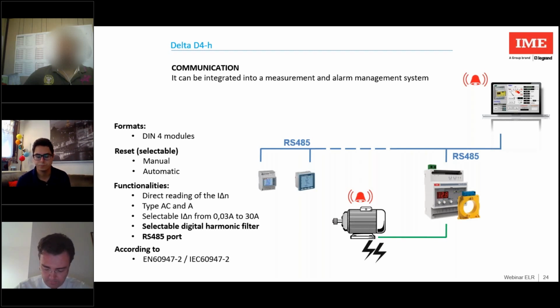From Marco: for equipment with harmonic filters, what is the maximum level of harmonic distortion of current allowed? Up to the 25th harmonic, it cleans the waveform. Pay attention that in many cases I have to use this reinforced filter only if I'm sure that my line has a lot of harmonic content. Helpful here, for example, is the NEMO range, the multifunction meters that show what the harmonic content in my circuit is. Because if I don't, I cannot be certain that it is a problem of harmonics.